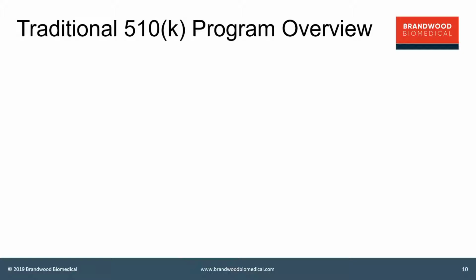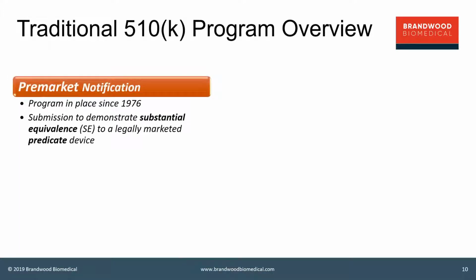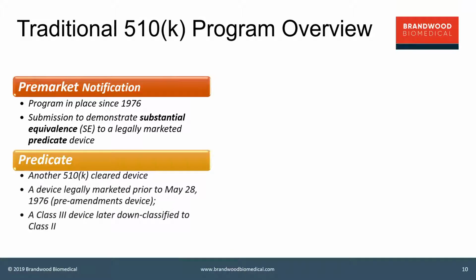So the traditional 510K program is then again the most common type of 510K, and it consists of obviously a very specific model. So it's a pre-market notification. That's a program which has been in place since 1976, so that's a fairly well-tested program, I would say. It is based on substantial equivalence to a legally marketed device, which we call a predicate. So we'll talk very briefly about those terms.